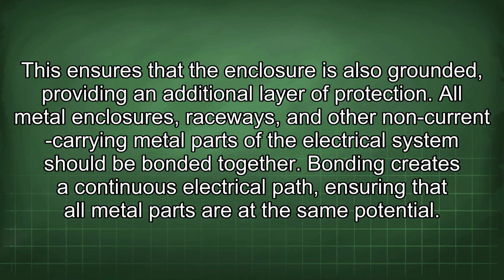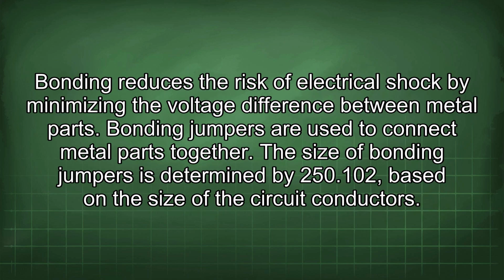All metal enclosures, raceways, and other non-current carrying metal parts of the electrical system should be bonded together. Bonding creates a continuous electrical path, ensuring that all metal parts are at the same potential. Bonding reduces the risk of electrical shock by minimizing the voltage difference between metal parts. Bonding jumpers are used to connect metal parts together. The size of bonding jumpers is determined by 250.102 based on the size of the circuit conductors.